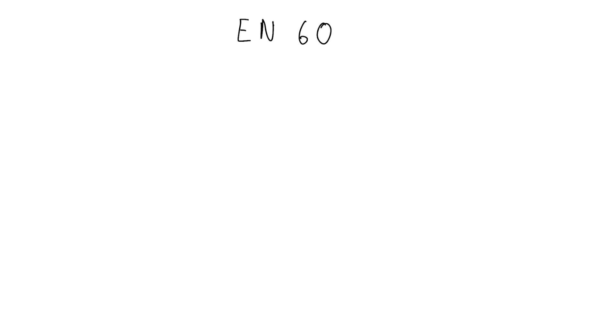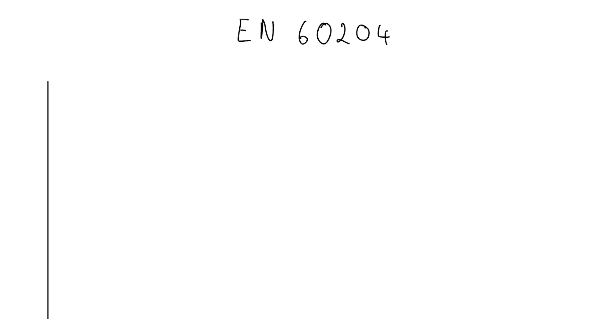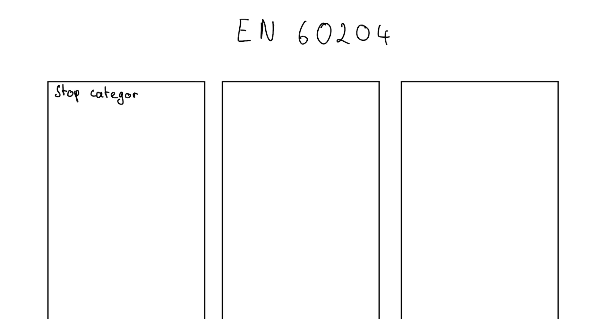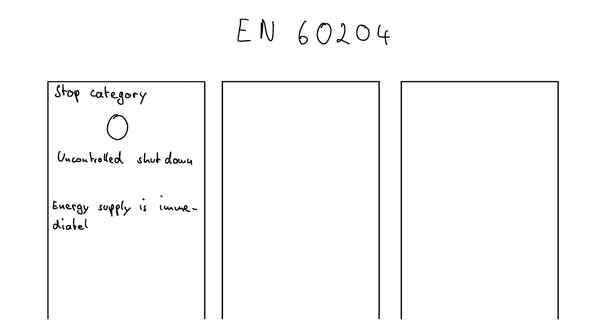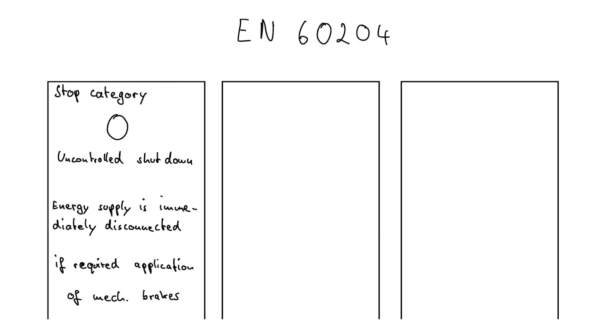It depends heavily on the application which safety function suits best. Our emergency shutdown safety relays work in accordance to EN 60204 with stop category zero. This means they shut down the power supply of an actor — for example, a drive — immediately.